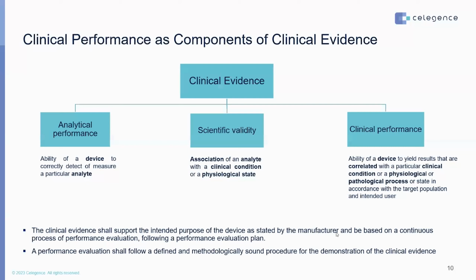Clinical performance is the ability of a device to show that there is a correlation between a particular clinical condition or a physiological or pathological process in a particular target population and an intended user. So, when we talk about a relation between an analyte and a clinical condition, it's scientific validity. Whereas when we talk about the device with the clinical condition, it is clinical performance. So that is a very small and minor difference between scientific validity and clinical performance. But the kind of data that you would use to support the scientific validity and clinical performance changes very greatly because of this small difference. So the clinical evidence, you will be using it to support the intended purpose of the device, as mentioned earlier, and that will form the basis for your performance evaluation.